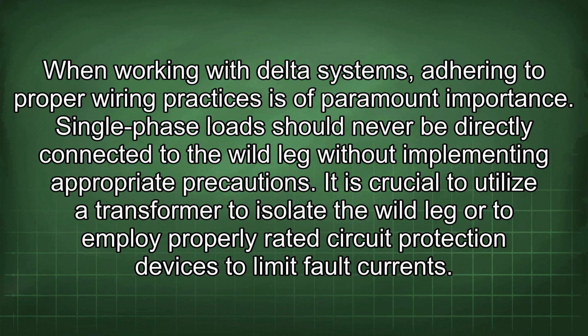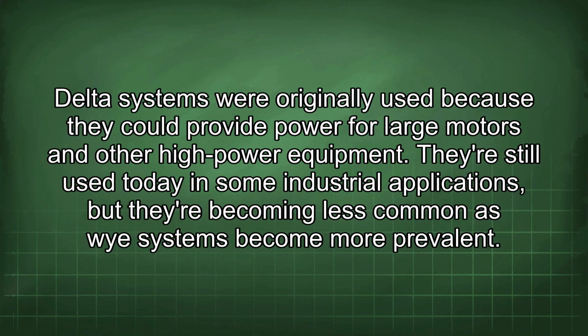When working with delta systems, adhering to proper wiring practices is of paramount importance. Single-phase loads should never be directly connected to the wild leg without implementing appropriate precautions. It is crucial to utilize a transformer to isolate the wild leg or to employ properly rated circuit protection devices to limit fault currents.